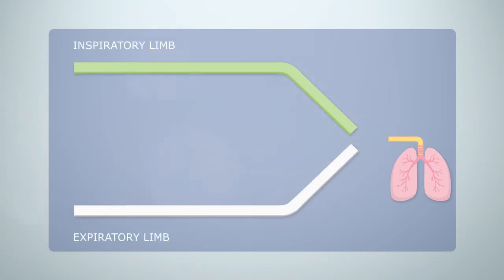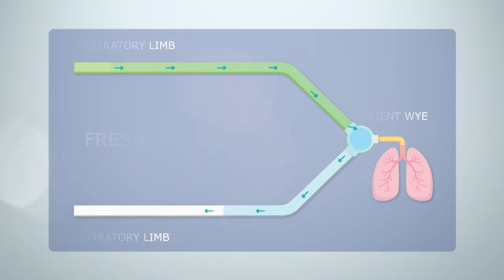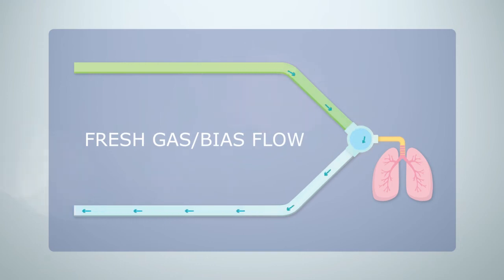A typical neonatal patient circuit consists of an inspiratory limb and an expiratory limb. A patient Y allows the circuit to be connected to the patient's ET tube and a constant 8 litres of heated and humidified blended gas is fed through the circuit. This is known as the fresh gas or bias flow and usually exits the rear of the ventilator without having any effect on the patient.